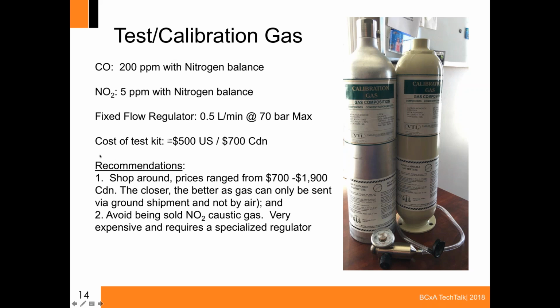The cost of the test kit can range. I got mine for right in around $700 Canadian, and that's because I shopped around. I tried to go through the local controls contractor, and they tried to give me the caustic one, so I needed a second regulator. That put it up to about $1,900, but then I got one from just one province over, about 800 kilometers, and I was able to get it for $700. So the closer you can get it, the better, because this gas has to be shipped by ground. It can't go by air, so that will reduce your shipping costs.